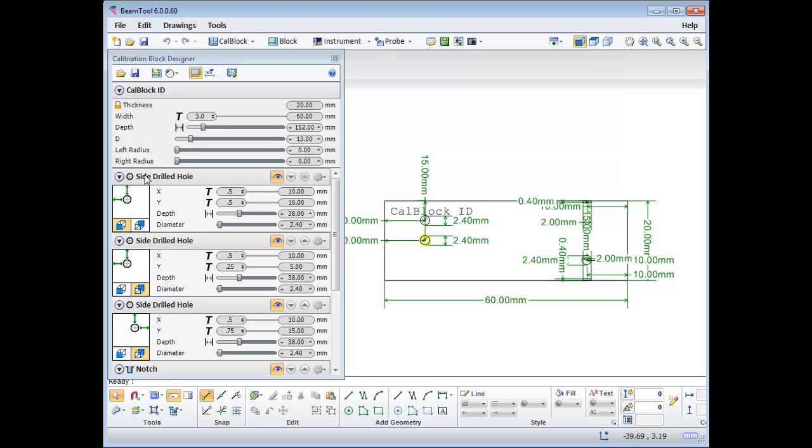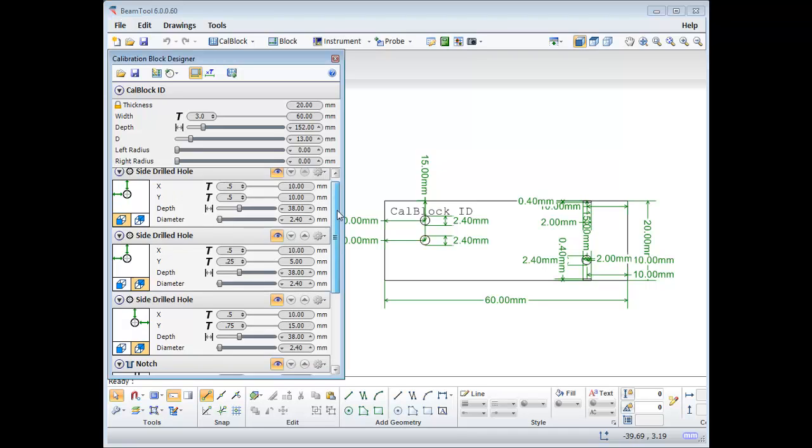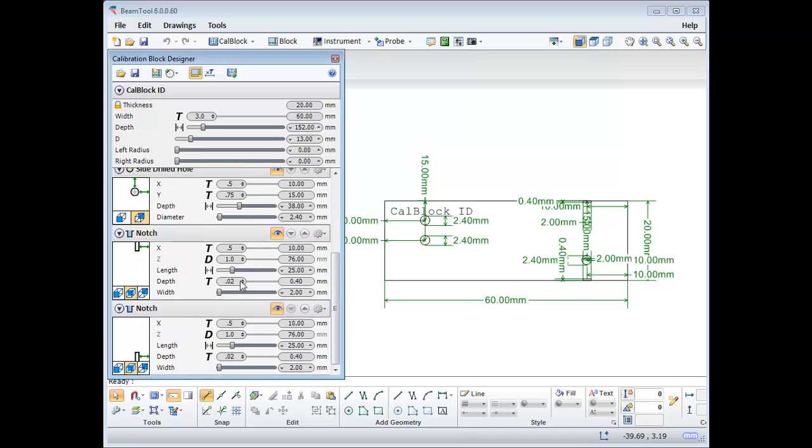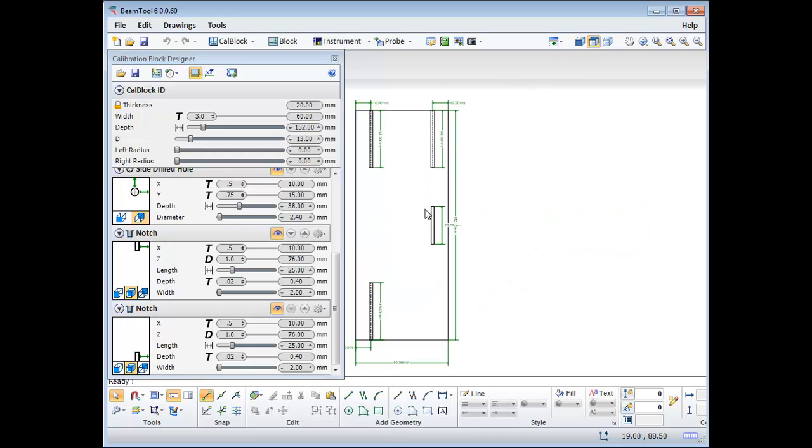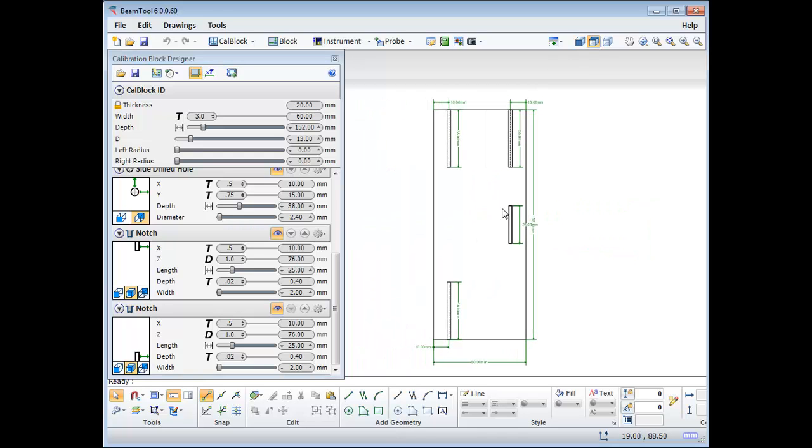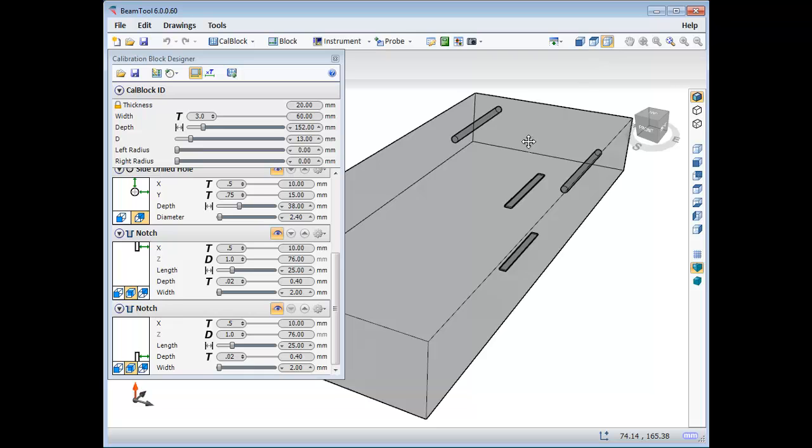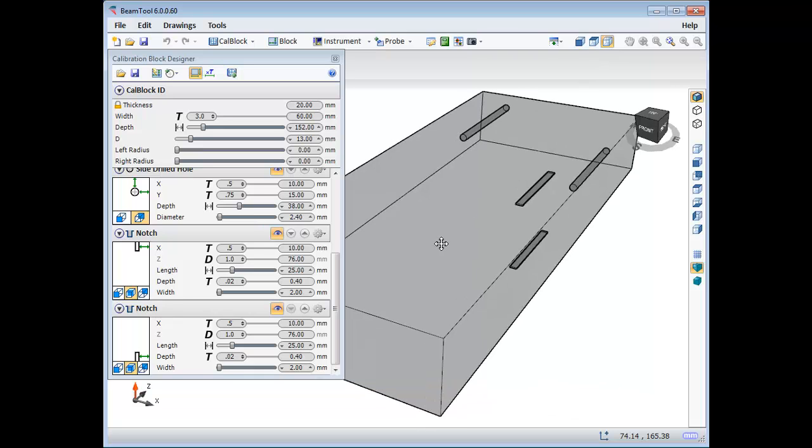Side drill holes will be added, the diameter and depth of them as stipulated in the code, as well as notches placed in the center of the block, the width and depth as stipulated, and the distance from the edge the minimum required. You can view your block from the top or in 3D for a better perspective of target positions.